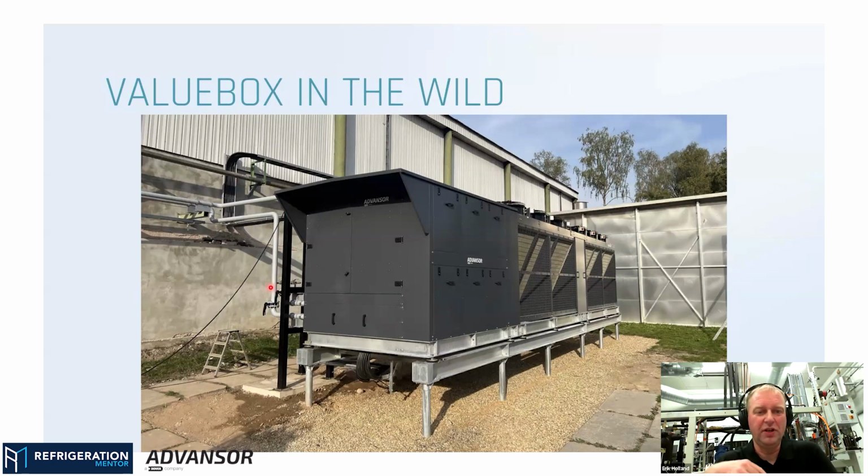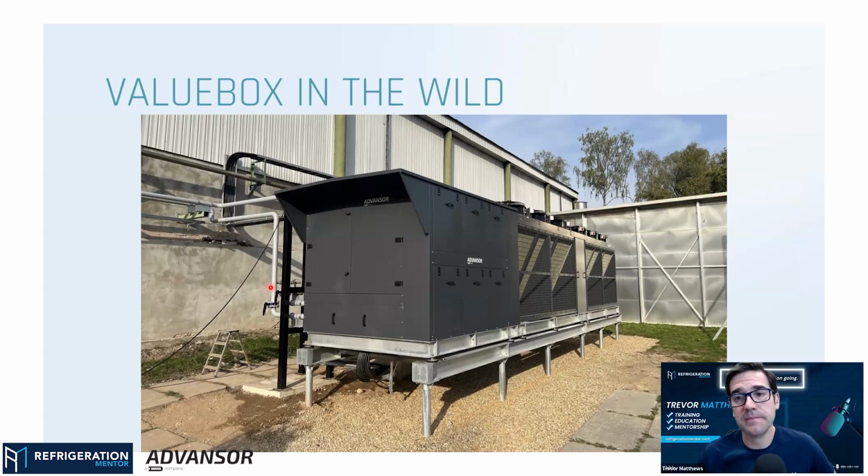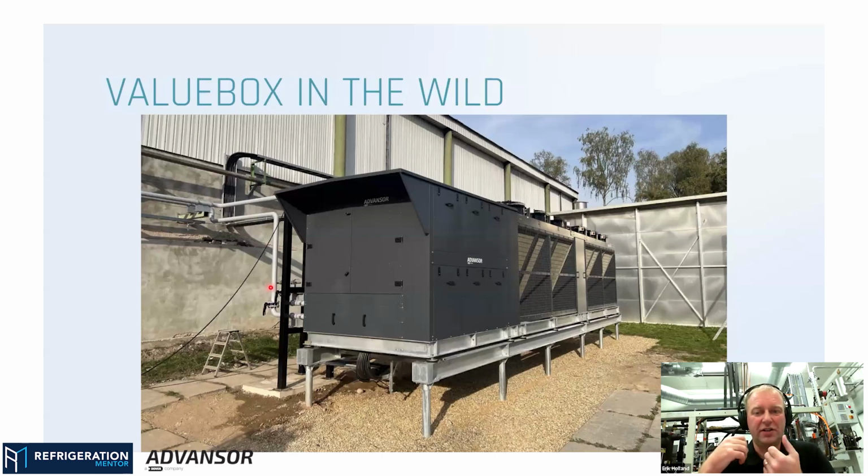If we convert it into European ways, then up here in the north in Denmark, where I am, the ejectors are not that important for the system to function properly, because we have a reasonably cold climate. But the further south you get, to southern France, to Spain, to Portugal, to Greece, when you go into these kinds of areas, then your high pressure gas will be so high pressure. Yep. That we are generating quite a bit of flash gas in your system.